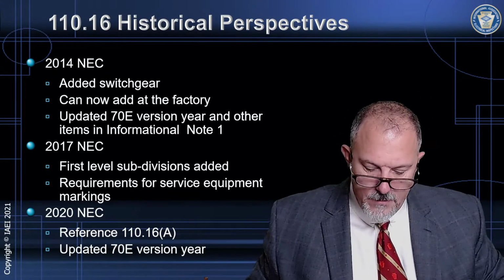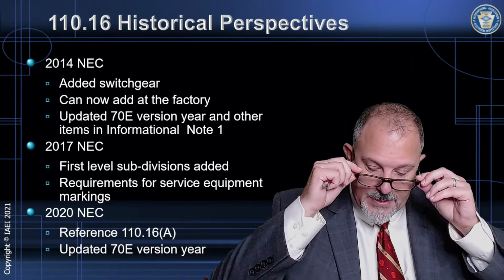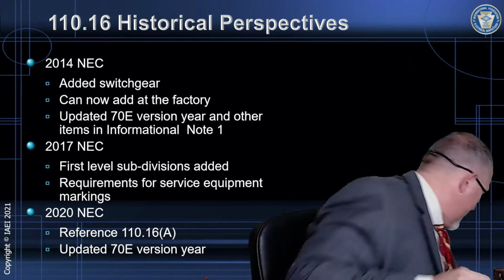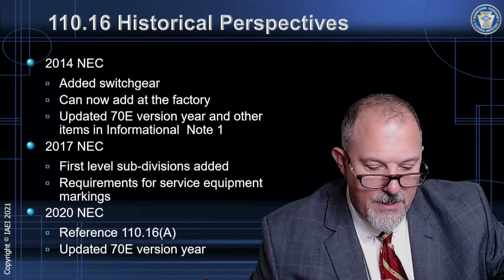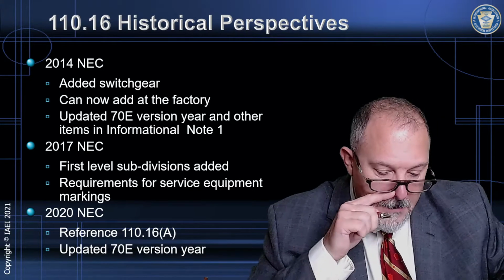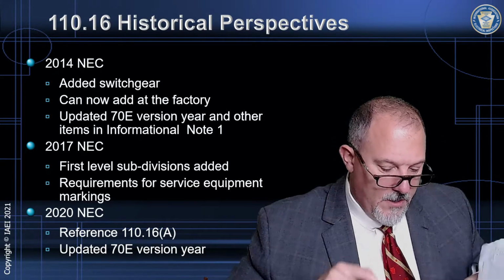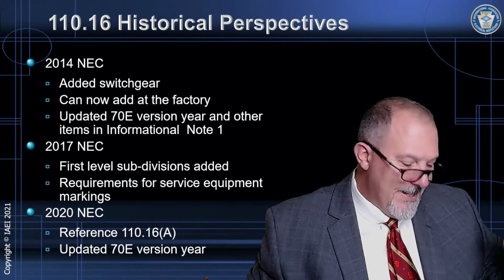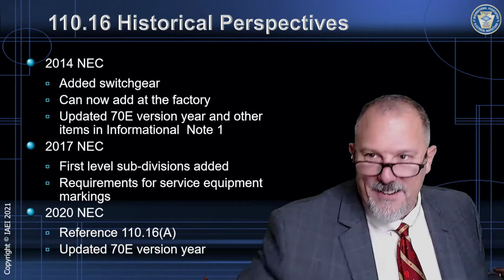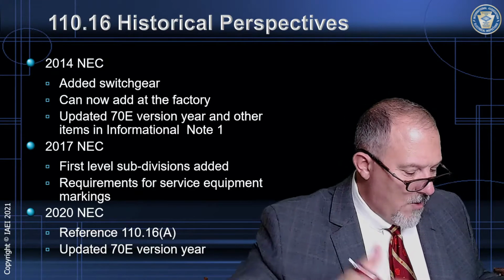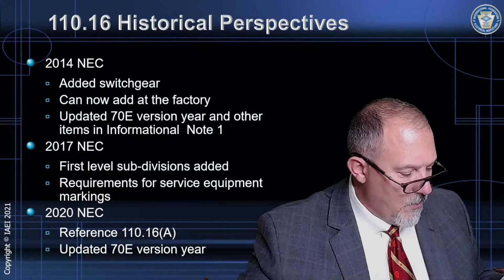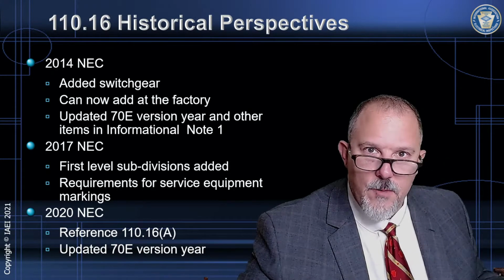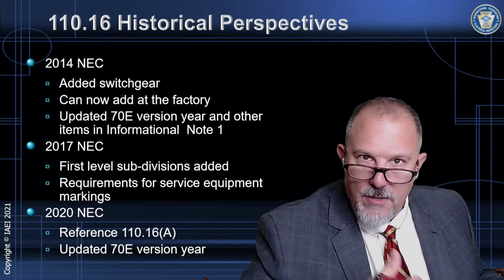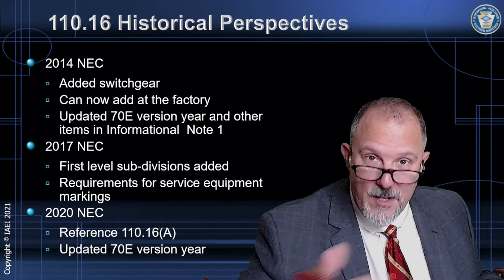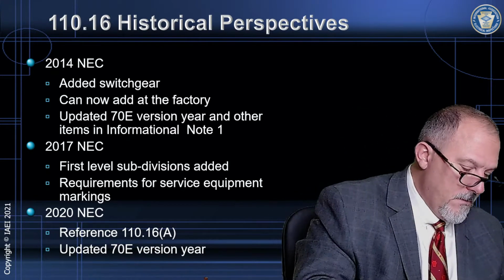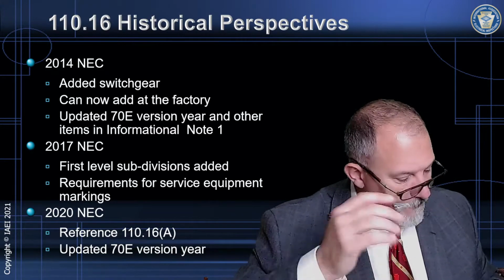All right, 2017, 110.16. Remember what happened in 17, and it still has the B. In fact, I'm going to go to the 2020 code because this is an interesting one. 110.16 in the 2020 code still says 110.21(B). I don't know about you, but I think that should be just 110.21, because why? It says the marking shall meet the requirements in 110.21(B). It should be 110.21 because what if the manufacturer puts the marking on? I don't have to follow 110.21, eh? Only if you do the field apply. That needs to be fixed. We've got to see. Anyway.